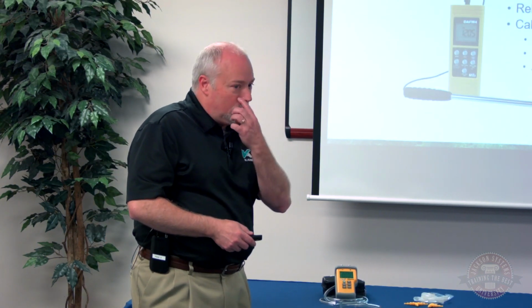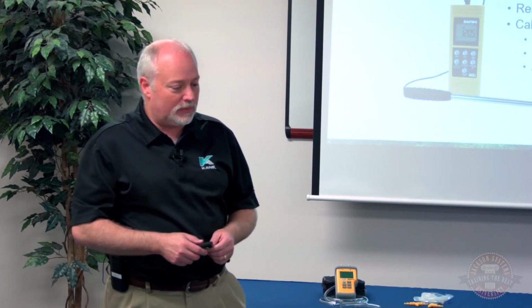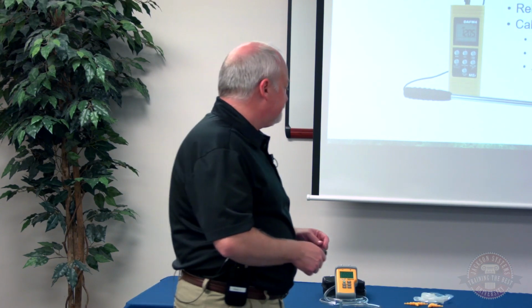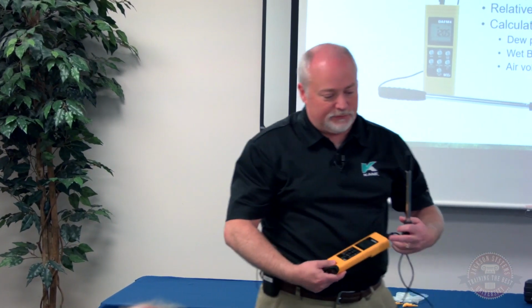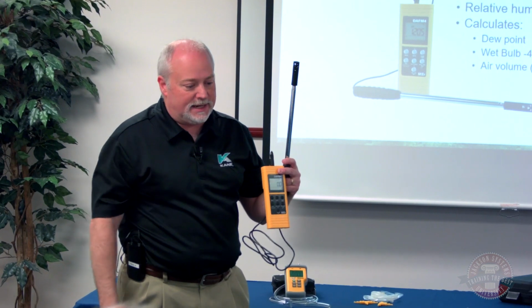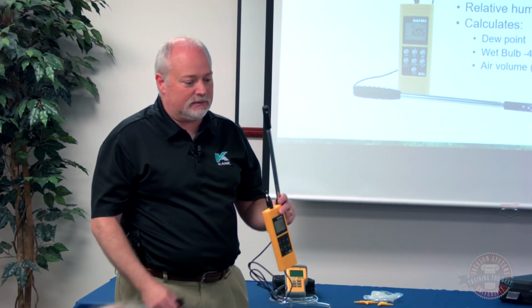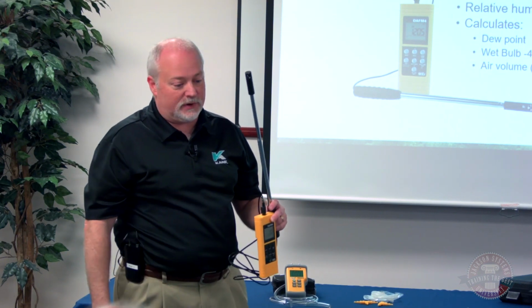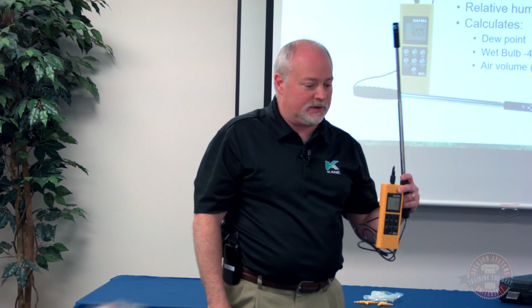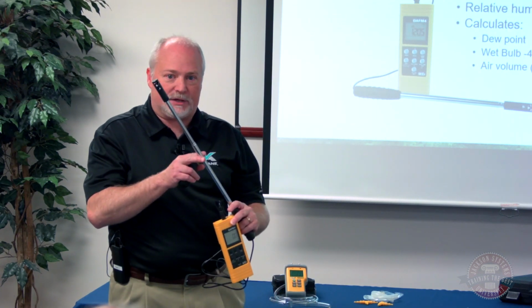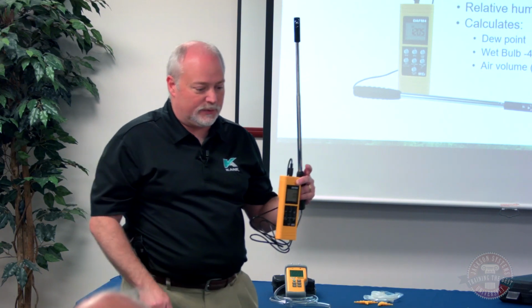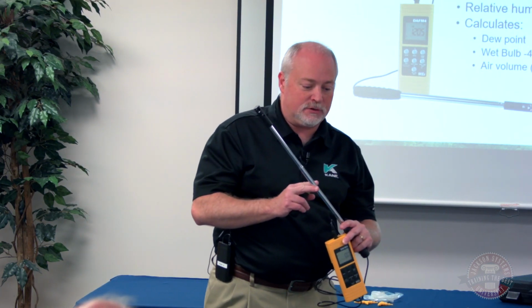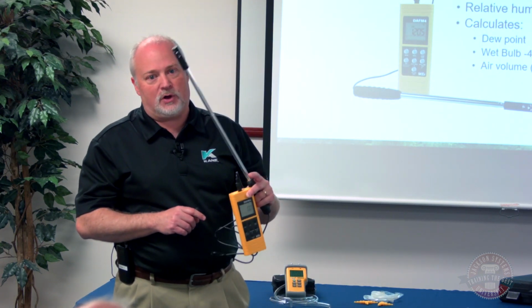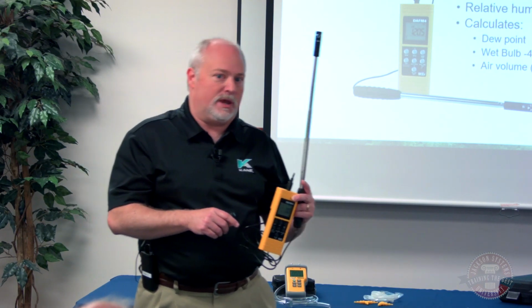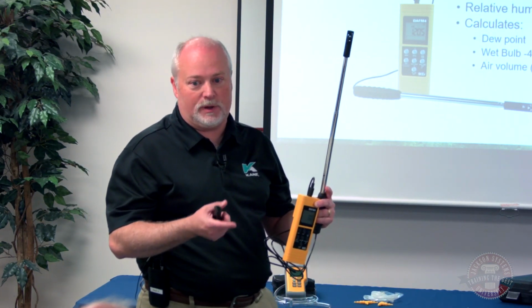All right. Well, let's move on then to our DAFM4. This is our digital airflow meter. Some nice features of this unit are that the anemometer reads anywhere from 99 to 3,937 feet per minute. Temperatures from -4 to 140 degrees Fahrenheit. Relative humidity from 0.1% up to 99%. So those are the readings that it actually takes. Then the other things we can calculate: our dew point, our wet bulb temperature, and we can also calculate airflow volume if we put in the area that we're measuring, whether that be a round duct or a rectangle, by putting our length and width in.